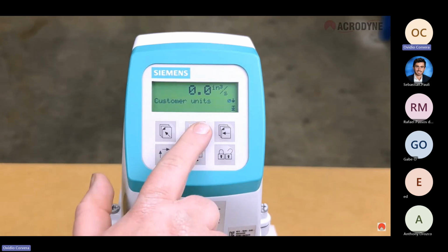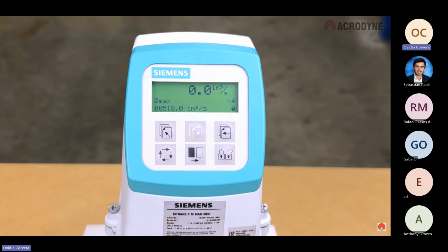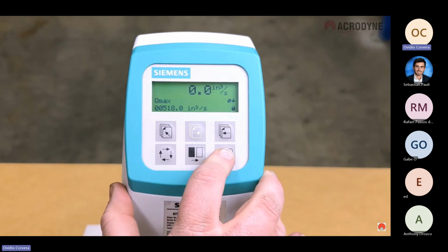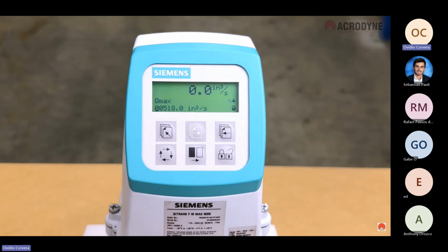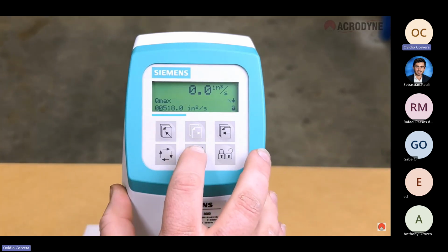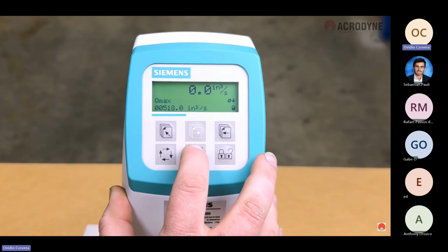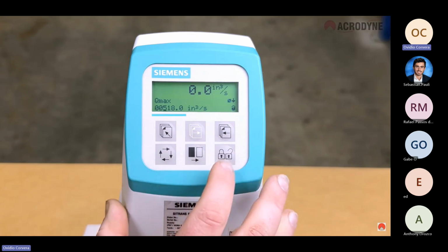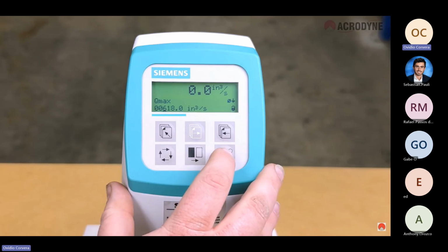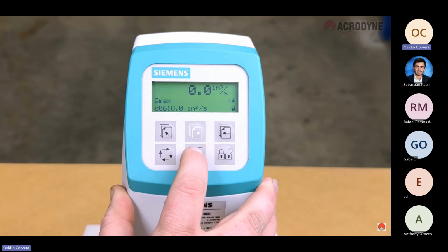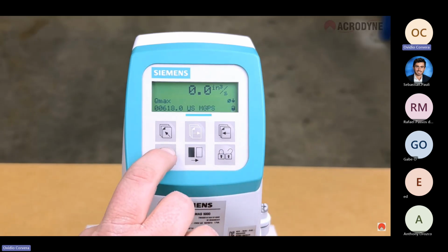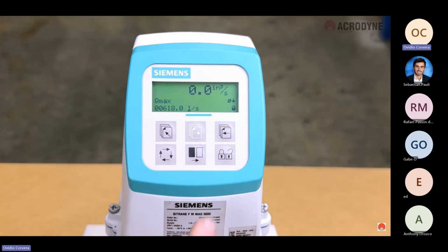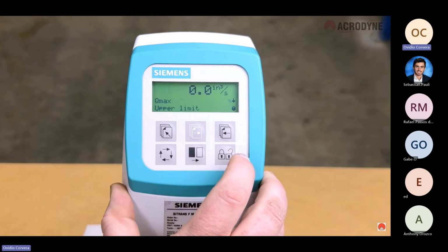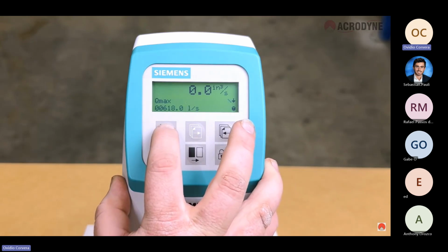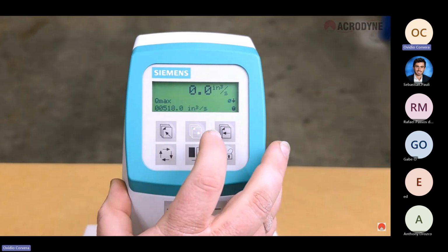Qmax. This parameter sets the flow span values and the units of flow. To edit these, press lock-unlock, and then use the select key to move the flashing icon to the field value that you want to change. Then use the change value key to cycle through the numbers. When the span value is correct, use the select key to move the cursor across to the units area. And then use the change value key to cycle through the desired units of flow for your application. We will use liters per second. When complete, press lock-unlock to save your settings, and then press the top-up key again to return to the basic settings menu level. Now press on the forward key to go to the next parameter.